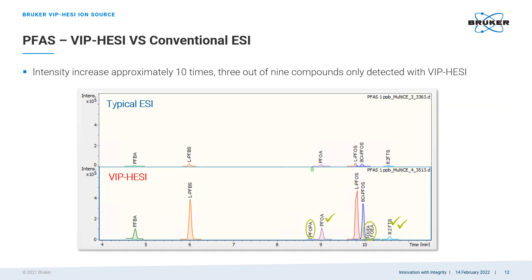Here is a comparison of a PFAS mixture analysis done with the same instrument using a typical ESI source on the top chromatogram and the new VIP-HESI source on the bottom one. The sensitivity improvement with VIP-HESI is approximately ten-fold. Three out of nine PFAS compounds in the sample could not be detected without VIP-HESI.